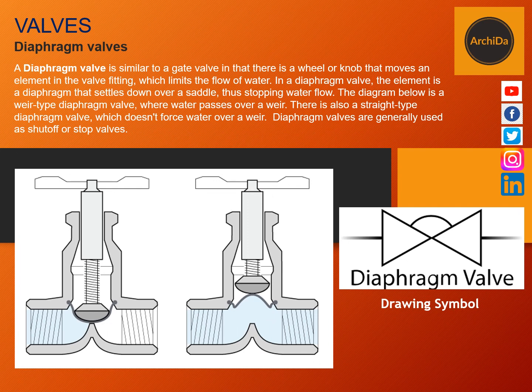A diaphragm valve is similar to a gate valve in that there is a wheel or knob that moves an element in the valve fitting, which limits the flow of water. In a diaphragm valve, the element is a diaphragm that settles down over a saddle, thus stopping water flow. The diagram shown is a weir-type diaphragm valve where water pressure passes over a weir. There is also a straight-type diaphragm valve which doesn't force water over a weir.